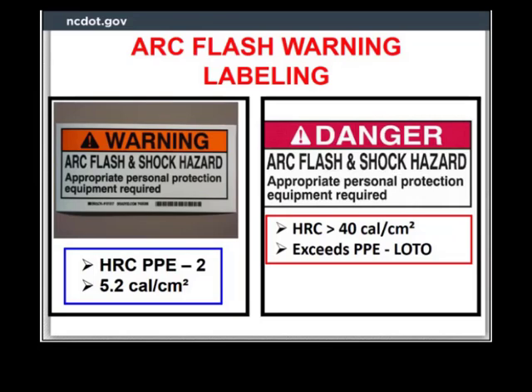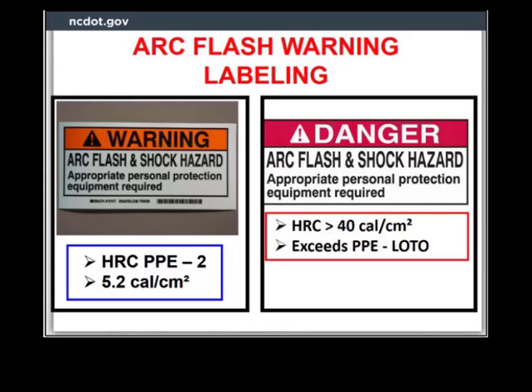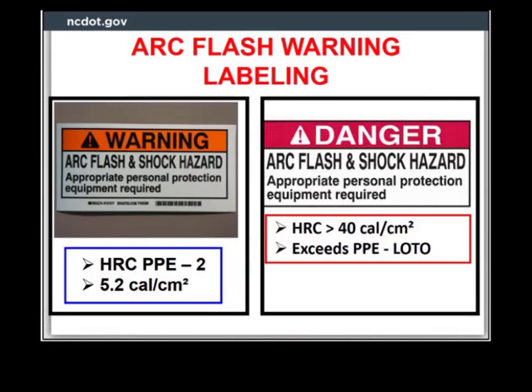Pictured at the top are both examples of generic arc flash labels. NFPA 70E requires what information must be included on the label. Prior to 2009, the top portion of each were acceptable. Later versions of NFPA 70E required additional information to be provided for the arc flash labeling. If an arc flash hazard analysis has been performed to determine the incident energy available, the electrical equipment should have an arc flash warning label listing the level of PPE required and the incident energy available as shown by the bottom label additions.